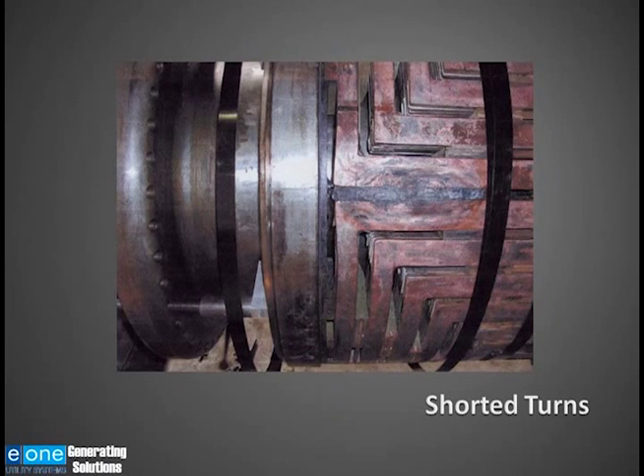This is an example of insulation failure in the turns of a rotor. Moisture, along with other contaminants, can form a conductive bridge, which can lead to electrical tracking or cause the insulation to deteriorate, causing a coil-to-coil short. As I mentioned earlier, there's a great paper written by the late Don Albright, founder of Generator Tech, that discusses insulation failure in detail.